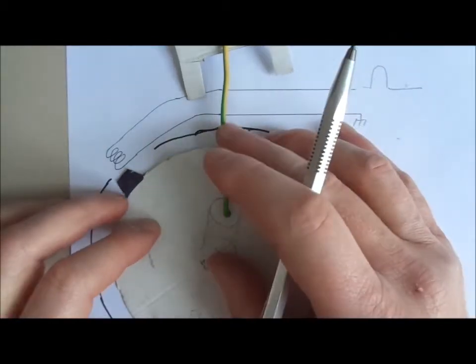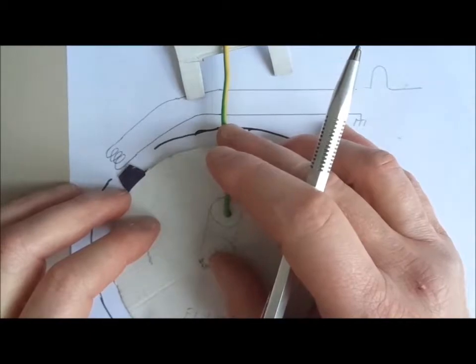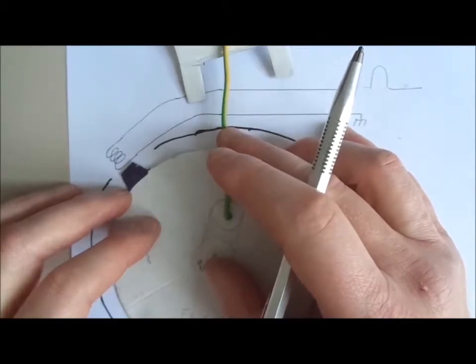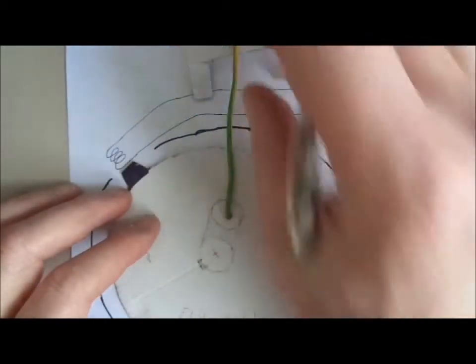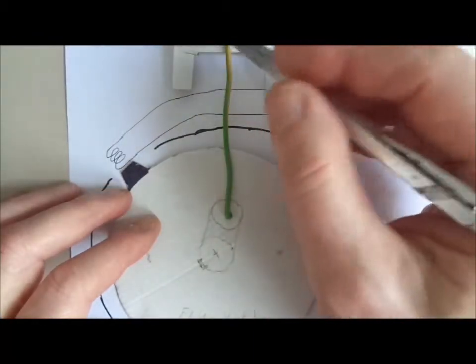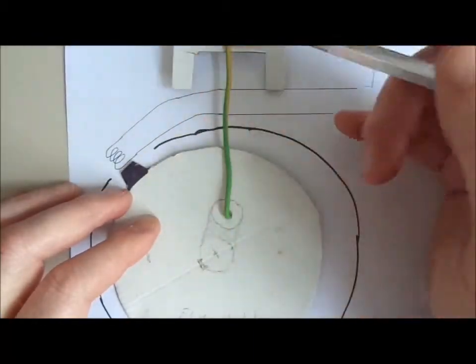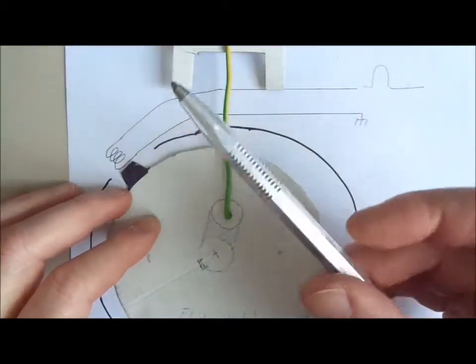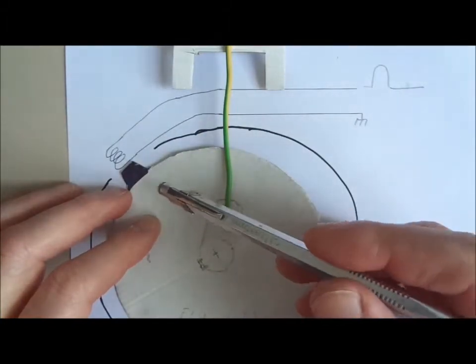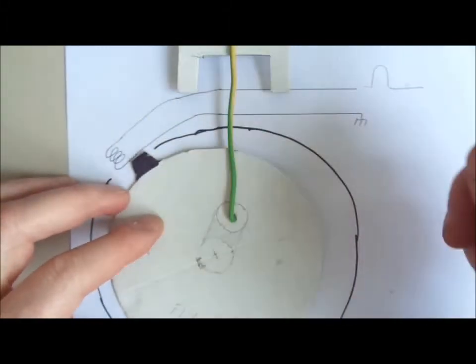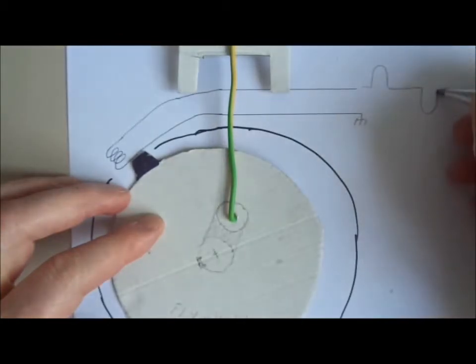And finally, the bar moves away from the pickup. At this moment, at this very moment, the piston reaches the top dead center. And when the bar moves away from the pickup coil, the coil produces a negative signal.